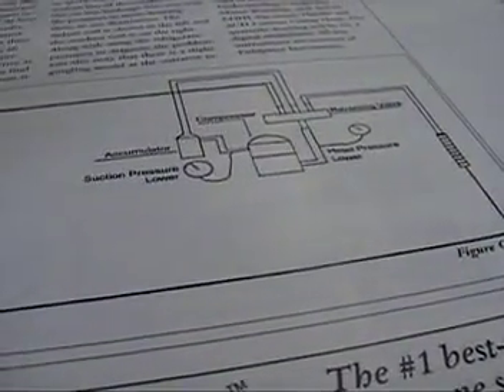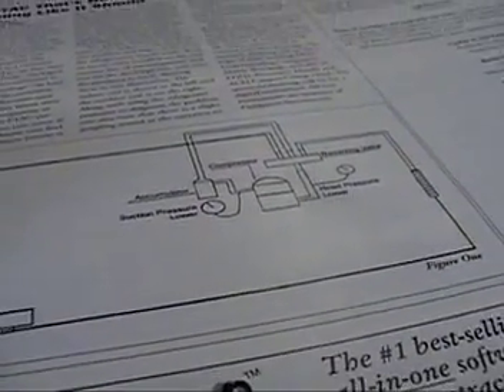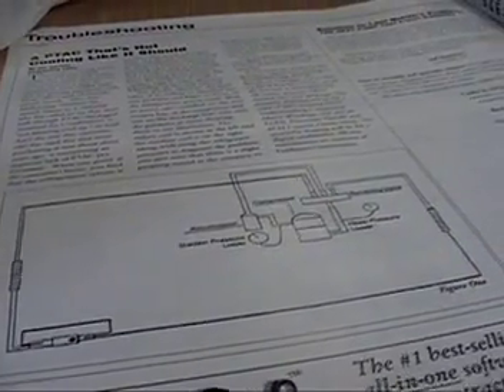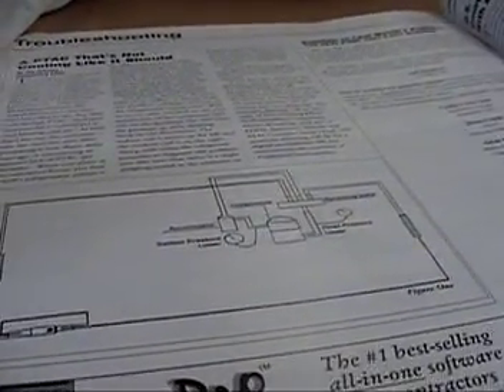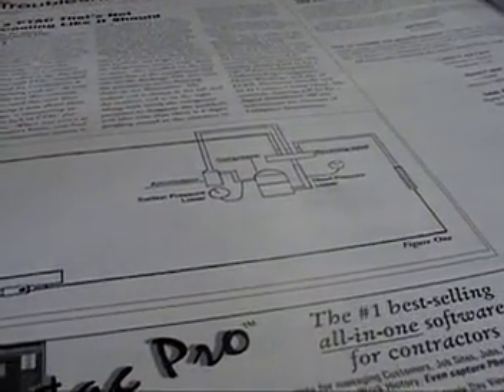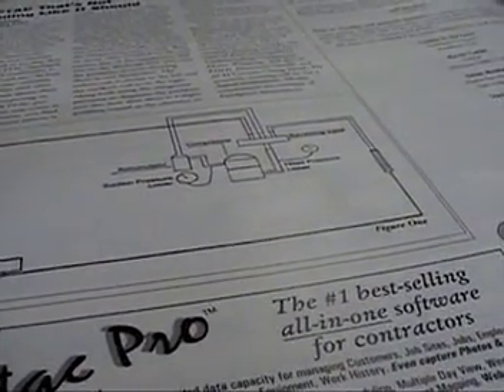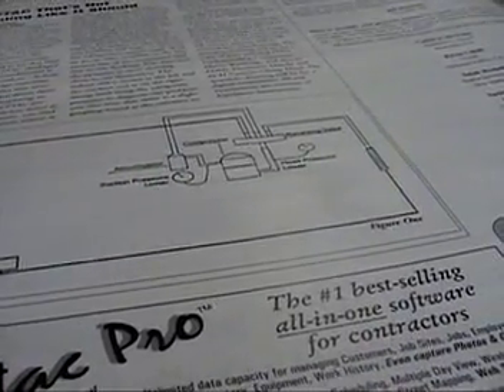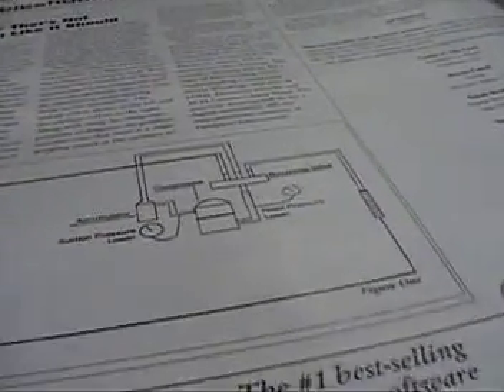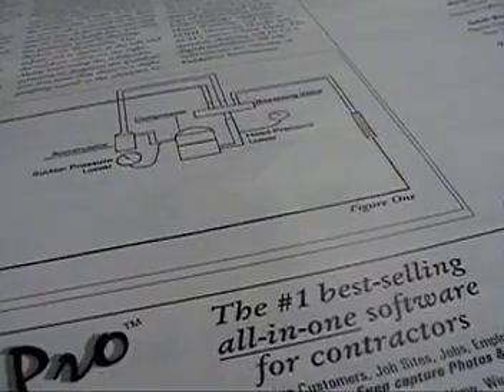And it stays on there. It stays on. Okay, and the true one would be, see what it says, low pressure, that right there is where you'd put it, anywhere between where it goes into the middle of the reversing valve, anywhere along there, you can go ahead and tap into it.